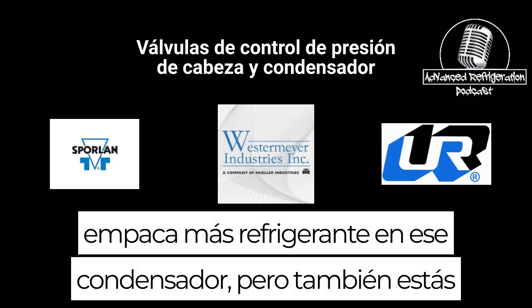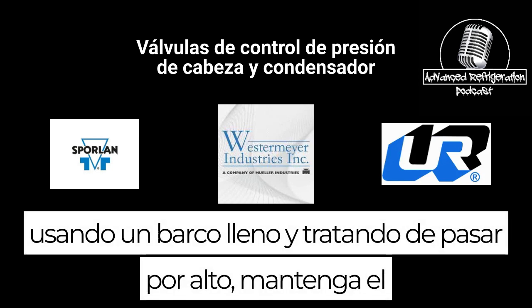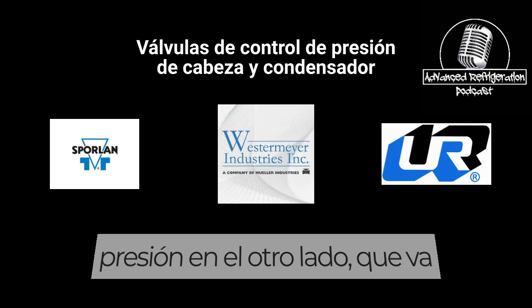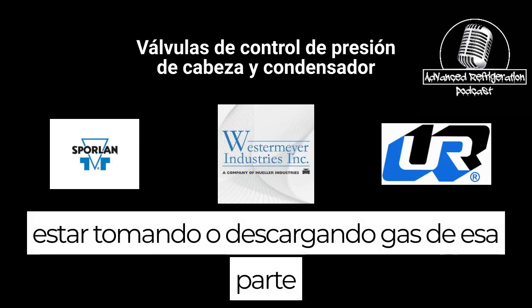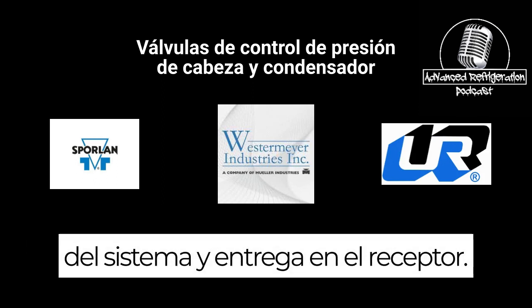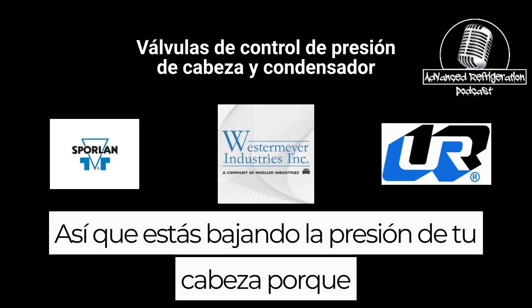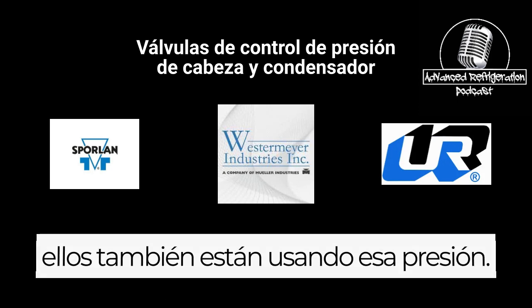If you see on the graphs where it starts going down dramatically, that means you're trying to pack more refrigerant in that condenser, but you're also using a boatload trying to bypass to keep the pressure up on the other side, which is going to be taking hot gas or discharge gas from that part of the system and delivering it to the receiver. So you're lowering your head pressure because you're using that pressure as well.